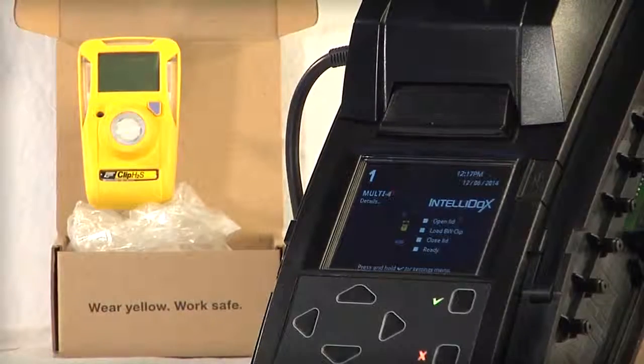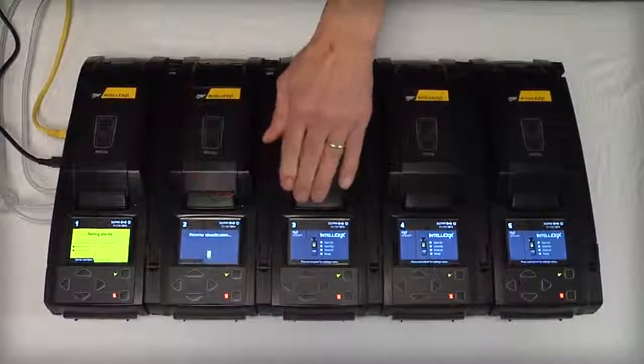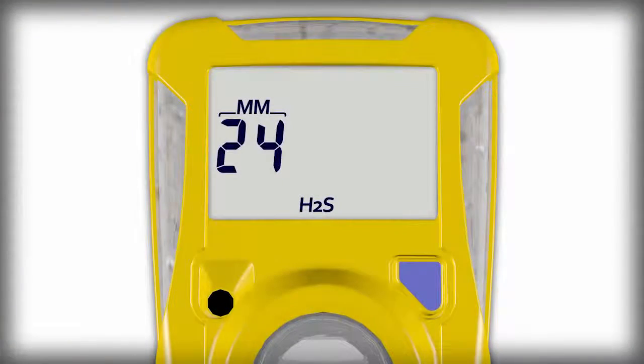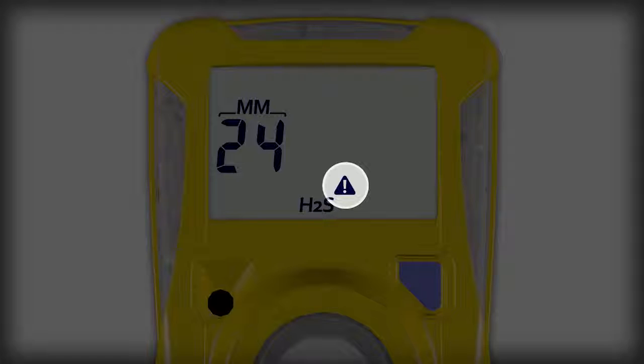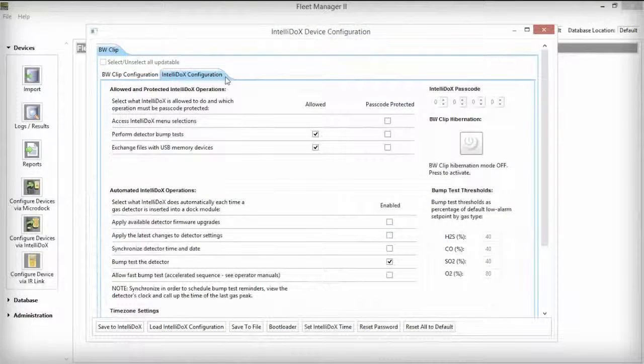Now, you can customize the default settings to create the BW clip configuration you want to deploy to a single detector or to a whole fleet of detectors. In this video, we will be configuring the BW clip's non-compliance indicator, which indicates when a BW clip has been exposed to gas vapors and has yet to be bump tested. Select the IntelliDOX Configuration tab. Make sure to enable Apply Latest Changes to Detector Settings and Synchronize Detector Time and Date from the Automated IntelliDOX Operations section.